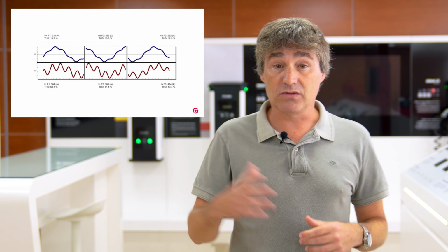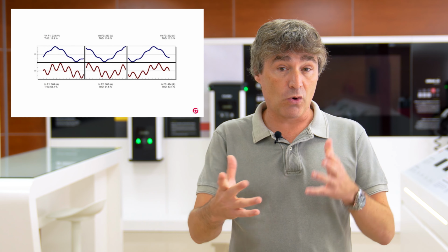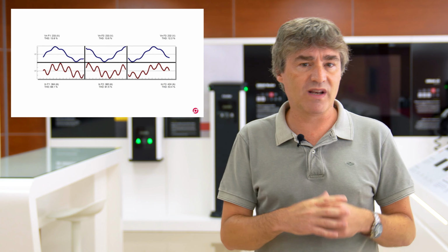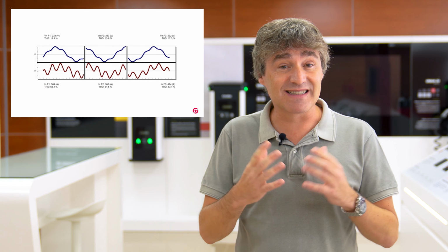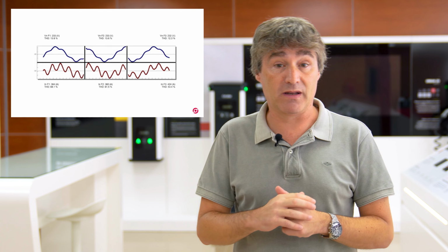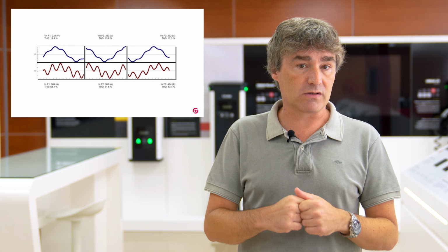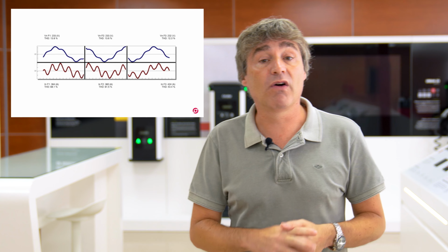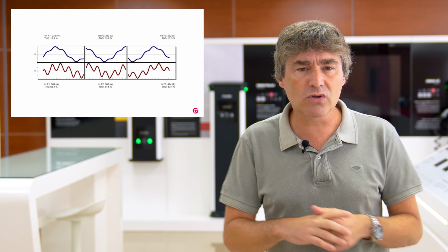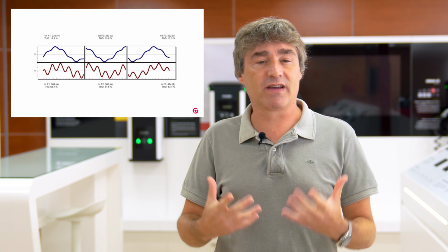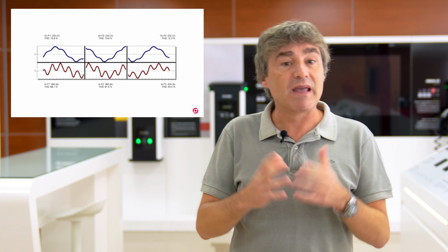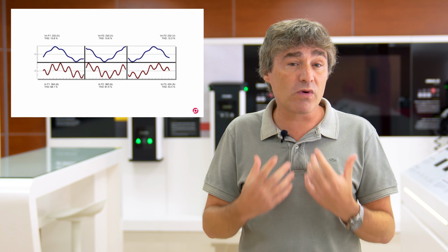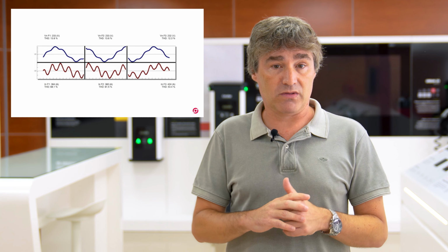Voltage total harmonic distortion rates are extremely high, over 30%, which for sure will eventually cause some loads to work incorrectly. But the most serious fact is that a harmonic amplification is happening. We can clearly count 5 cycles, that is, a resonance event of the 5th harmonic. This resonance not only means an extreme overload of the capacitors, which will probably not be able to withstand it for a long time, but also that the power transformer is working under untenable conditions.